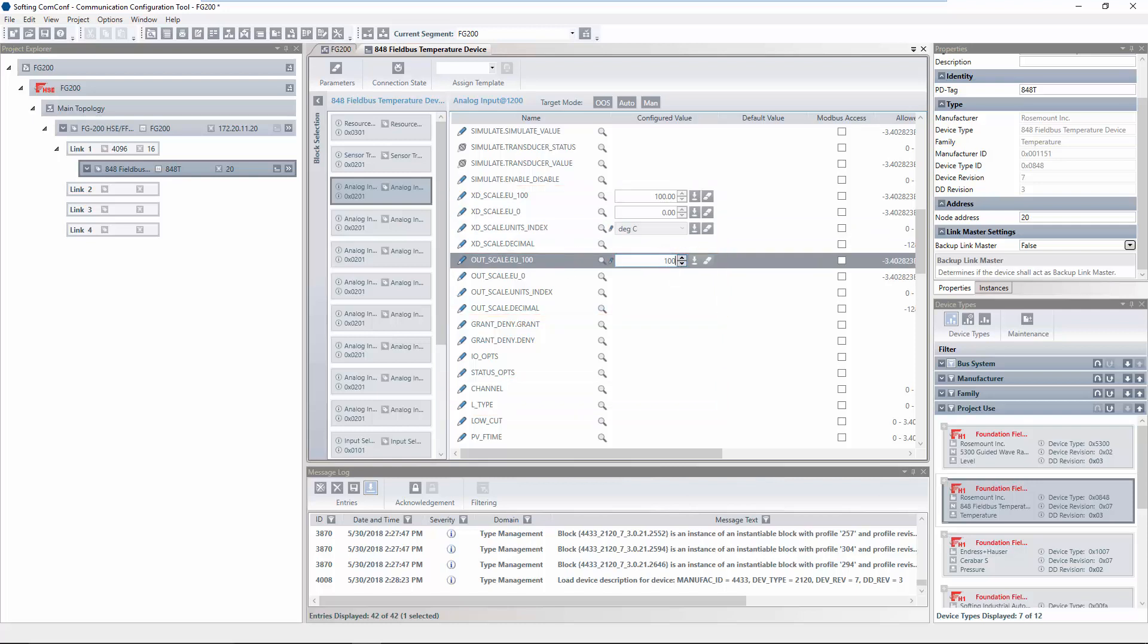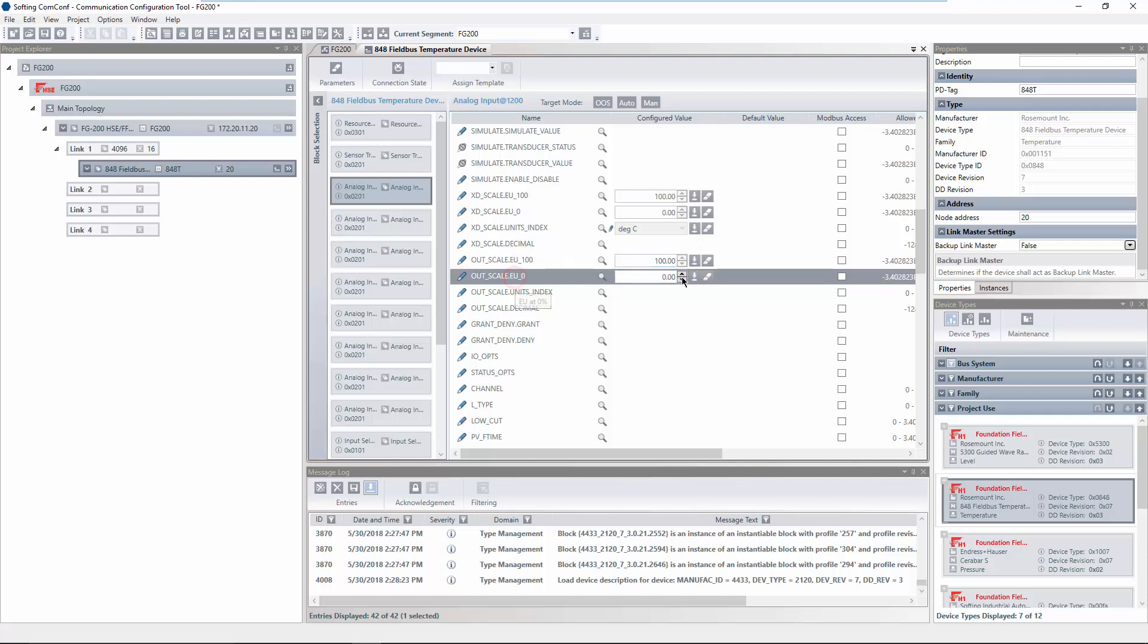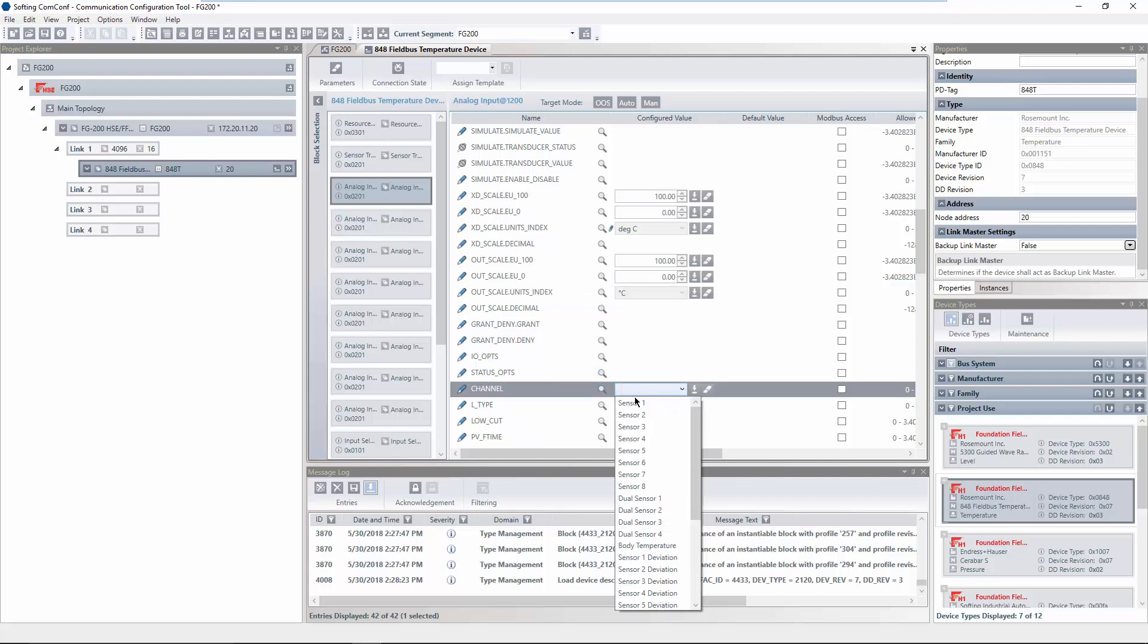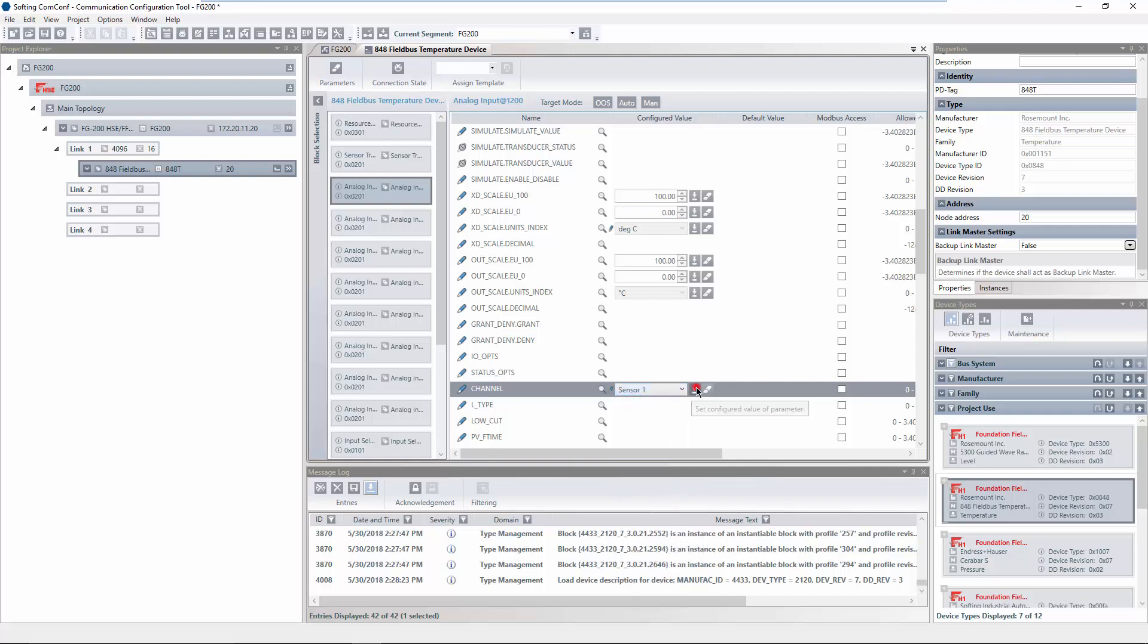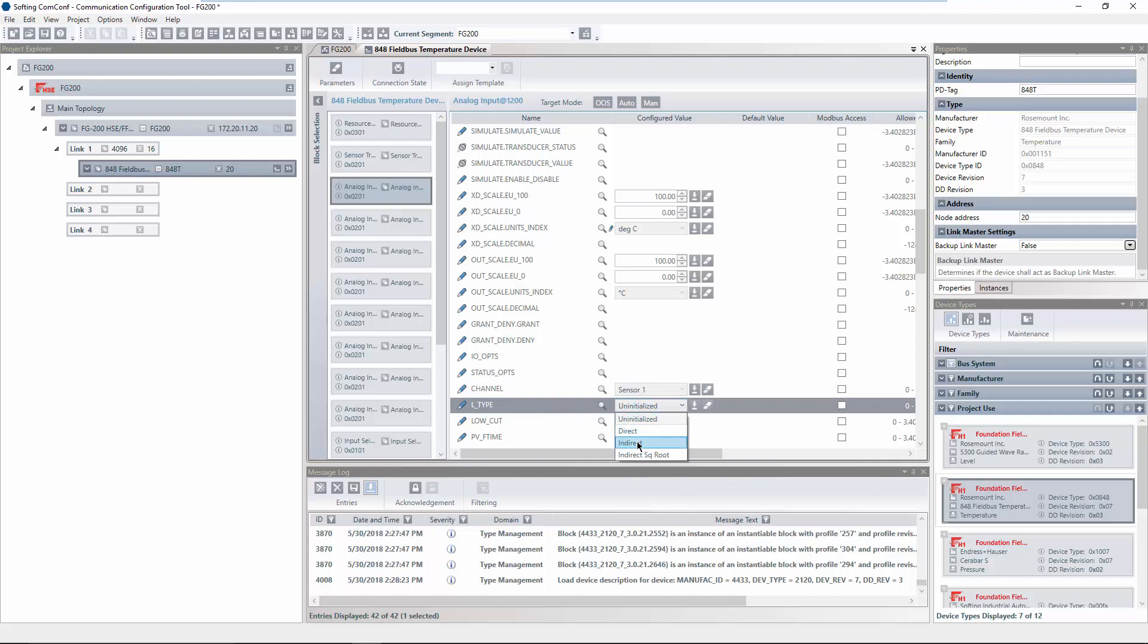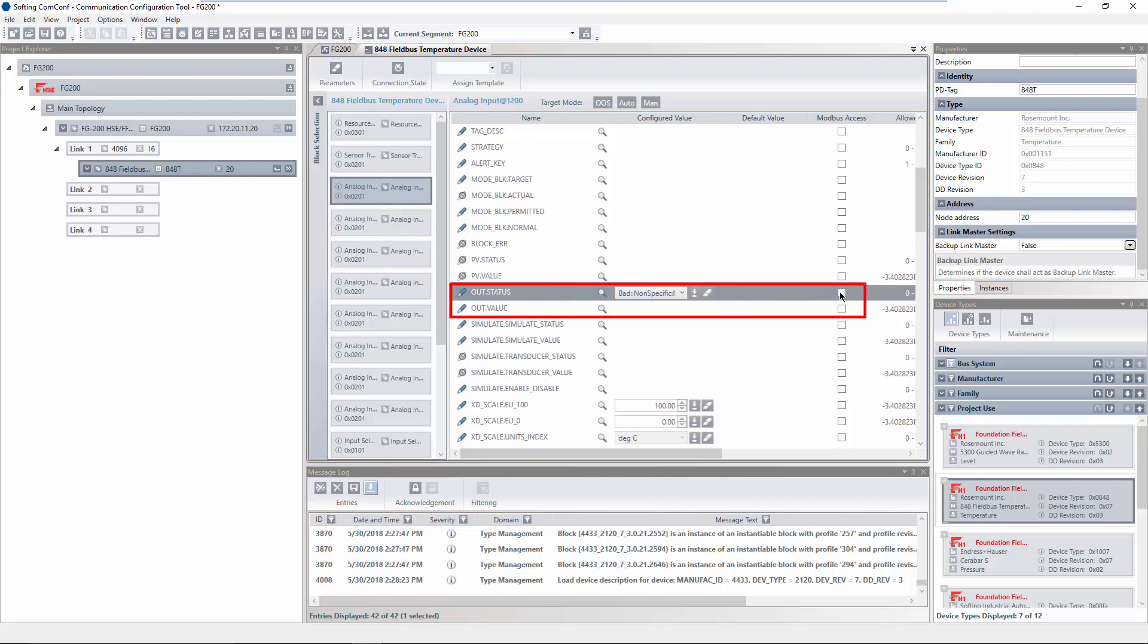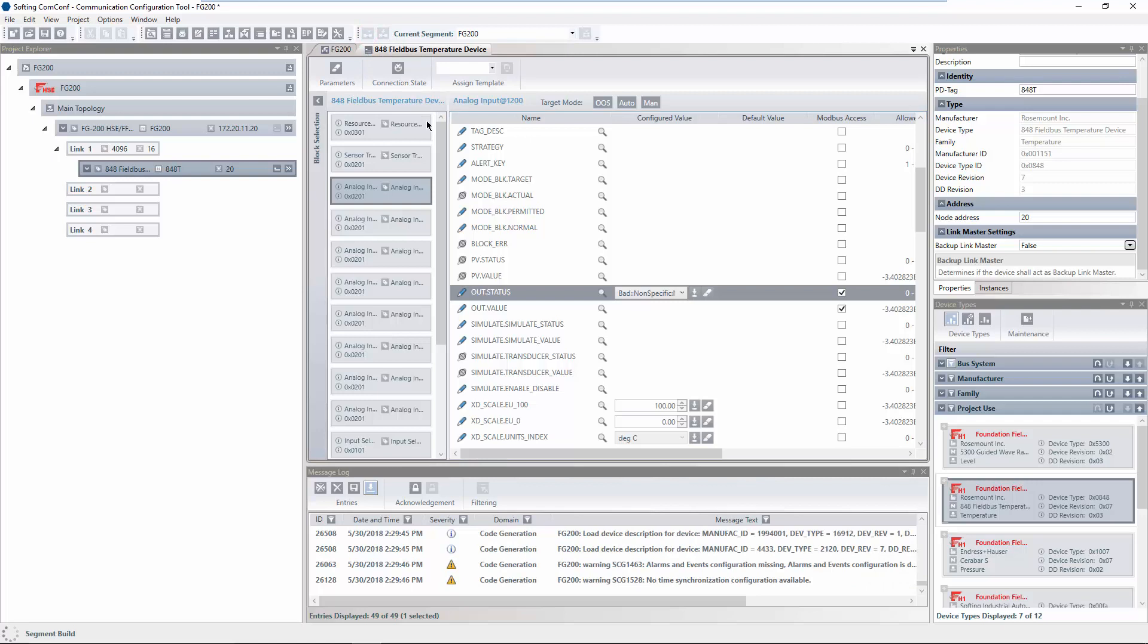In order to configure a parameter, you have to select it and insert the desired value in the column Configured Value. Click on the symbol to set the value to add it to the configuration. Select the parameters OutStatus and OutValue and activate the option Modbus Access to access the process value and the corresponding status via Modbus. Click on Build Current Segment to validate the configuration and generate code to download to the devices.